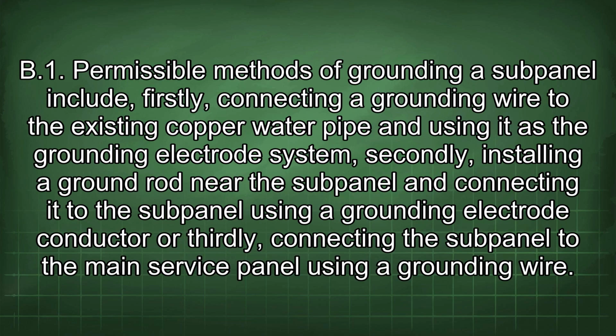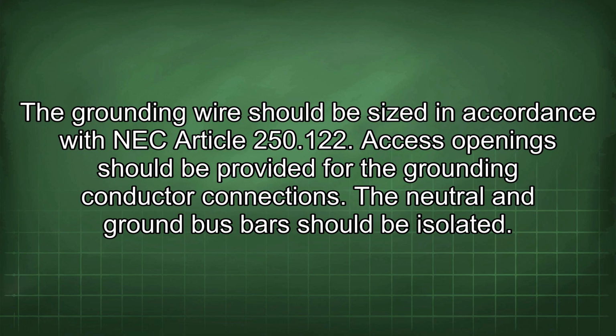Permissible methods of grounding a subpanel include: firstly, connecting a grounding wire to the existing copper water pipe and using it as the grounding electrode system. Secondly, installing a ground rod near the subpanel and connecting it to the subpanel using a grounding electrode conductor. Or thirdly, connecting the subpanel to the main service panel using a grounding wire. The grounding wire should be sized in accordance with NEC Article 250.122. Access openings should be provided for the grounding conductor connections. The neutral and ground bus bars should be isolated.